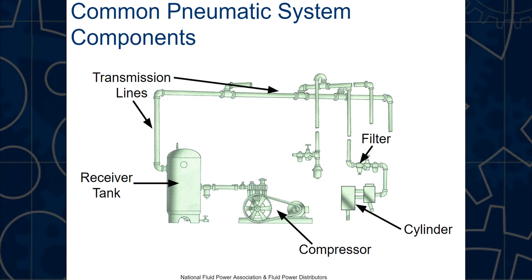The filter removes dust and condensation water from the line so it doesn't enter the rest of the system. The regulator controls the pressure going out — for example, you might have 100 psi in the tank but only want 50 psi going to the equipment. Drains allow removal of any water or condensation that develops inside the line.